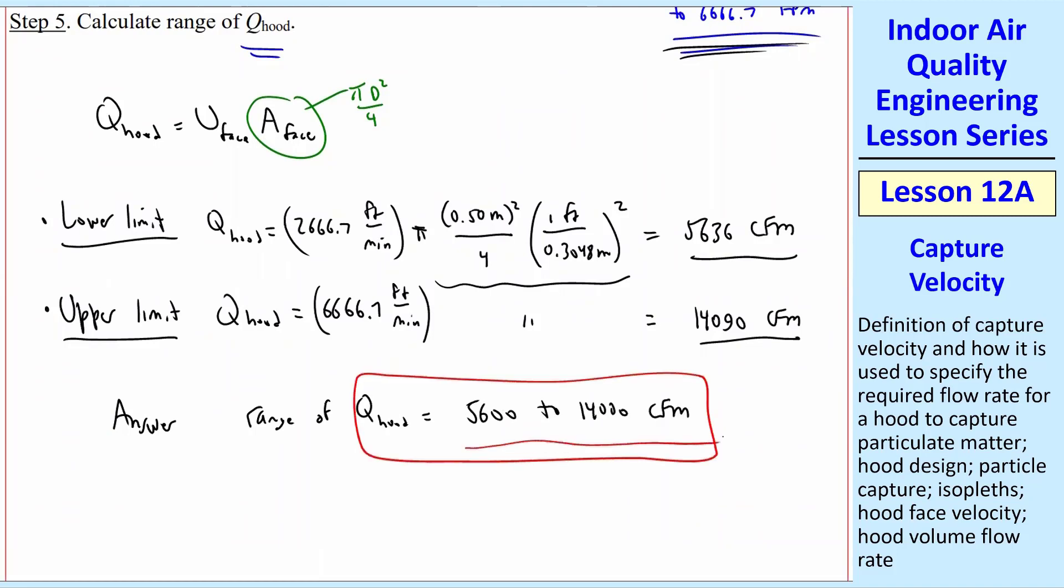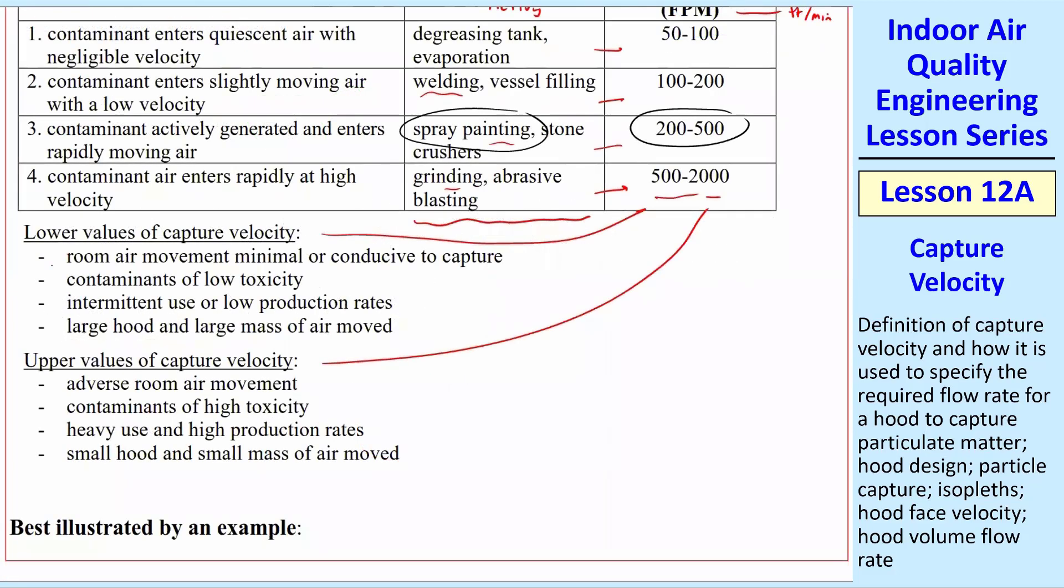Which of these are you closer to, the lower value or the upper value? Well, you go back to the table. If there's very few room movements, and so you can capture these easily, they're low toxicity, et cetera, you'd use the lower values. If there's lots of bad stuff going on, lots of room air movement, et cetera, high toxicity, you use the upper limit.